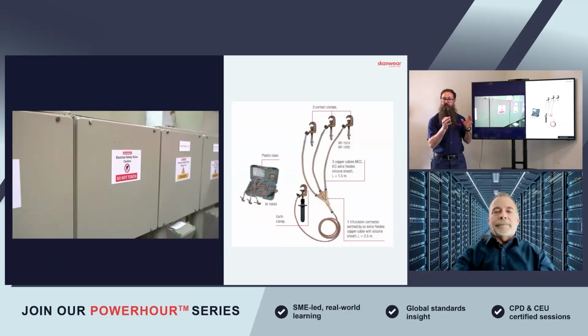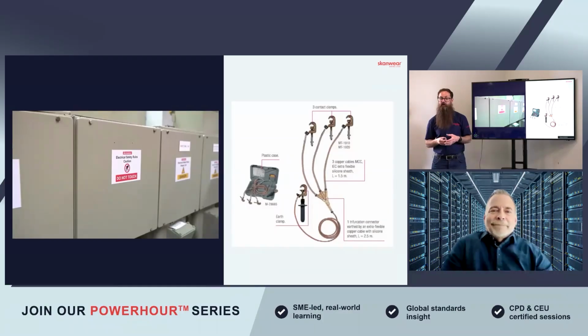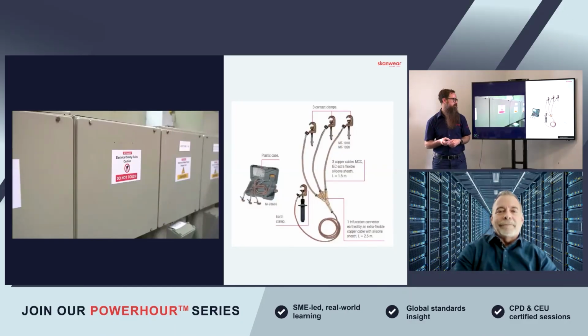So we might do the circuit main earth application at the primary substation like we're going to do now, but then at the zone, we might establish a zone of work and apply a portable ground closer to the equipment. We might even put on a comfort earth or a portable earth at the location as well, just to give us that belt and braces that we know it's definitely going to discharge any stored energy and capacitance that might be induced into the cable.